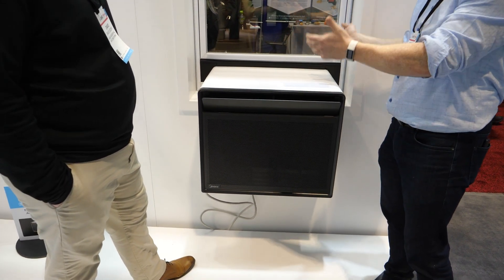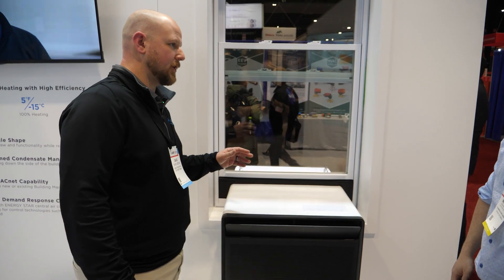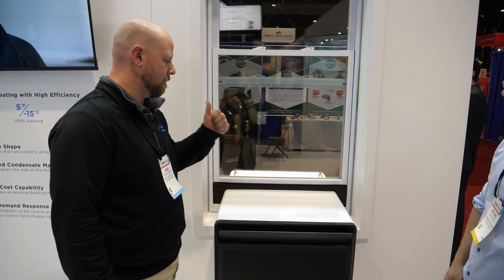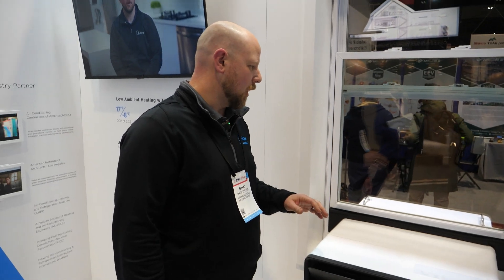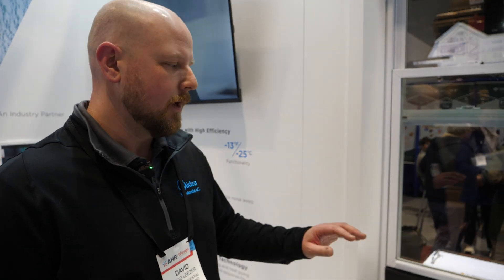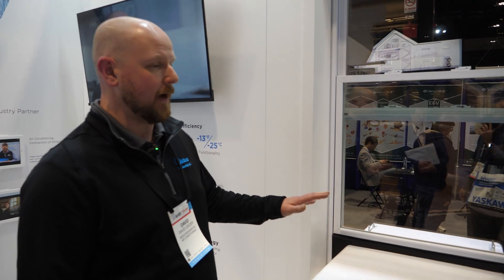What I like about this is it's an easy drop-in 115-volt appliance that we can slip into a window that does heating and cooling with no infrastructure upgrades. You literally just plug it into the wall and you're done. That was a lot of what their specifications said — they wanted a window-mounted, high-efficiency, cold-climate-capable heat pump on a 15-amp circuit so they didn't have to do any huge electrical upgrades. It's 9,000 BTUs of heating at 17°F and 9,000 BTUs of cooling, with 100% heating capacity all the way down to 5°F.